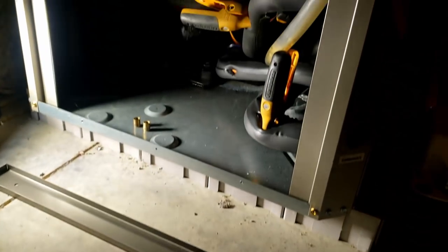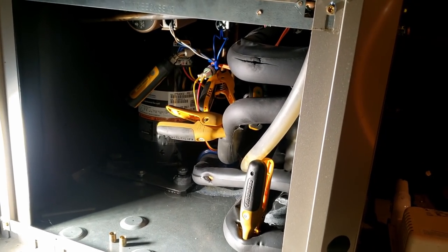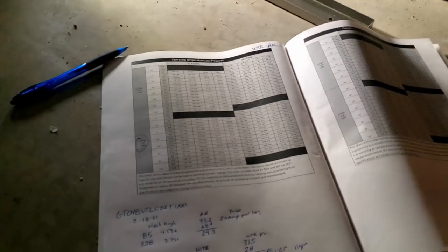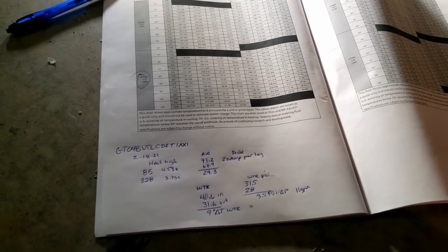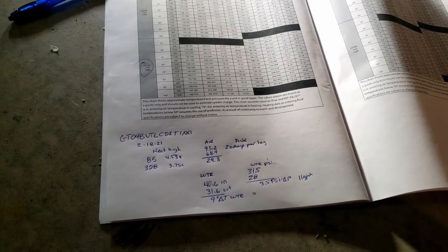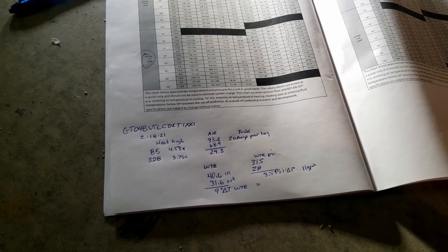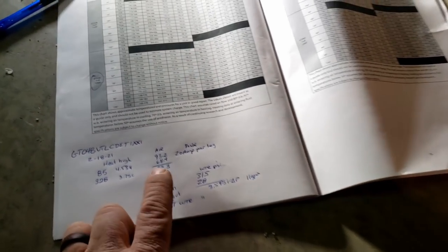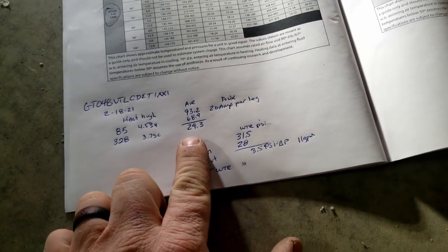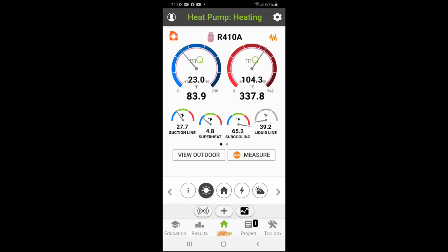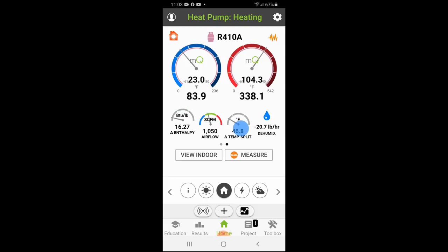Alright, so we've just begun checking it over. Went ahead and hooked all the probes up, got everything checked out. I've checked the auxiliary heat - I have 20 amps per leg which sounds right. I checked the resistance prior to that. Air rise is right around 24.3 degrees. Subcooling you can't calculate right now because I literally have that one unhooked. There's our supply and returns, and calculated airflow looks like it's right in line.